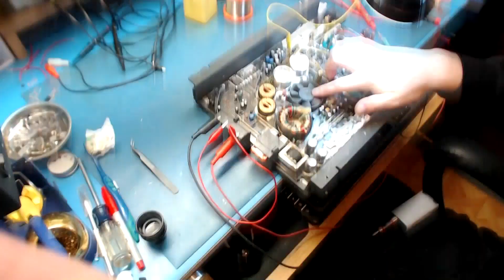I'm going to pull the leads out of the fan and see if we get any voltage on the pins that's supposed to drive the fan. So what I'm going to do is measure the fan terminals without plugging in the fan to the socket itself, and see what we get for voltage at those pins. Let's turn this on, that might tell us something.